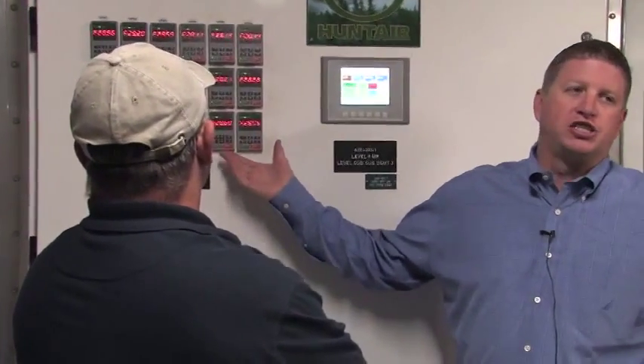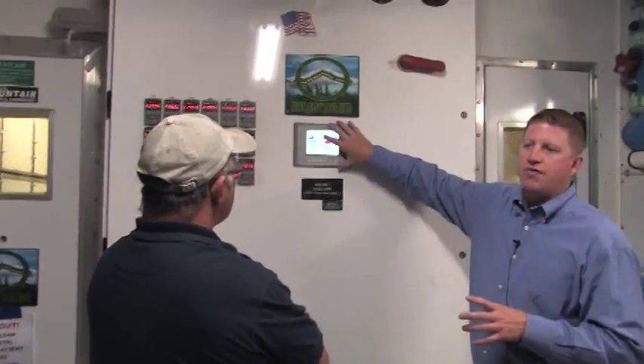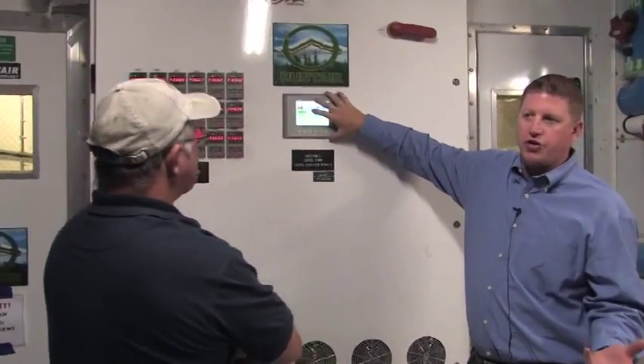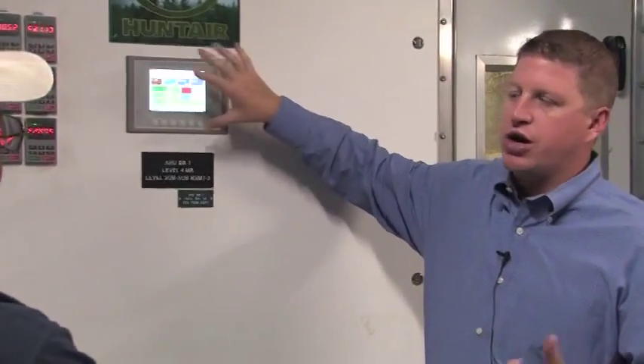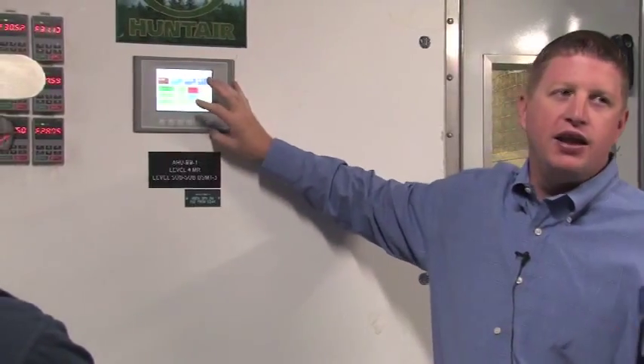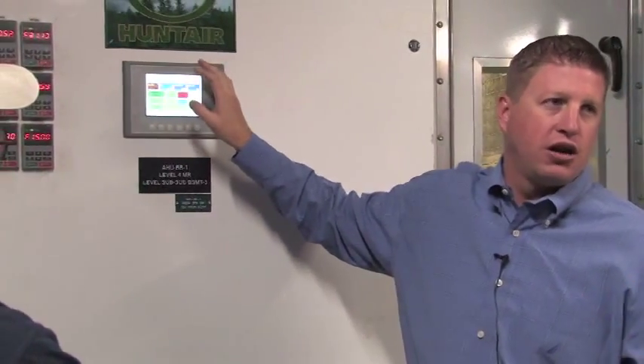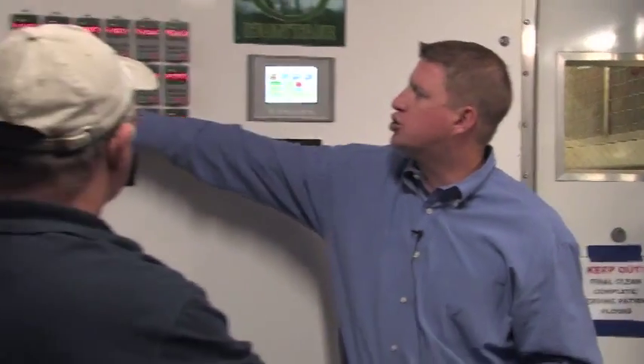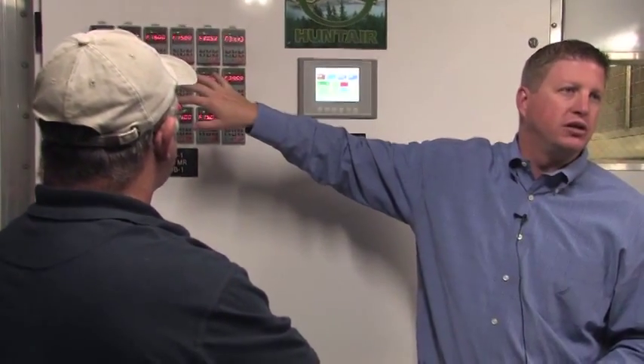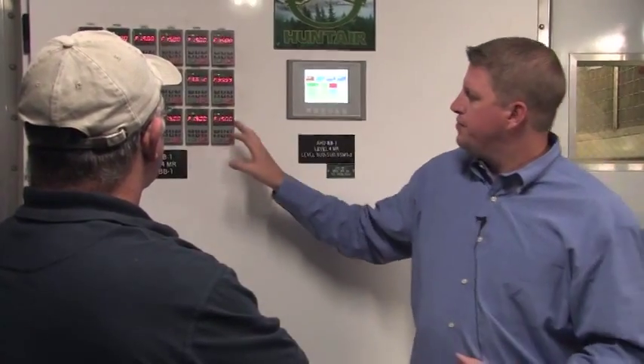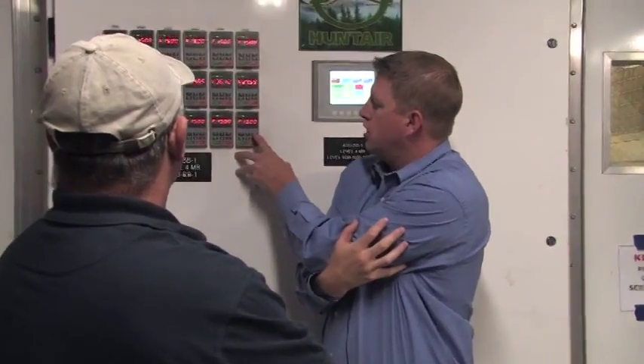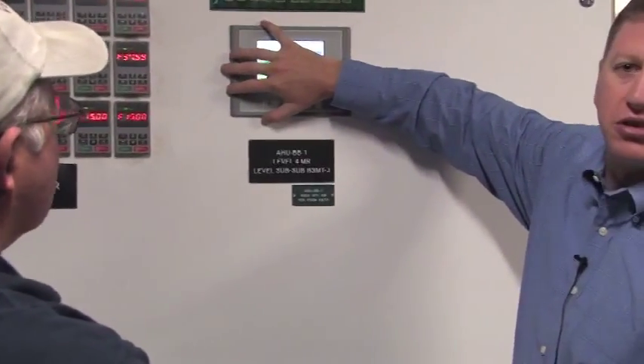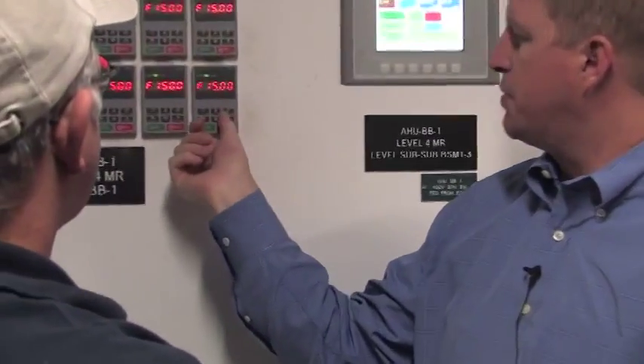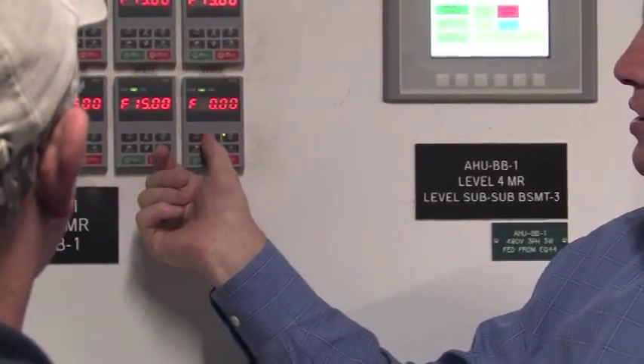So we're going to go through actually a scenario. The levels of redundancy are very deep in this, in that if this screen were to ever die, you could still control the unit through the BMS. In a situation where you lost this screen and the BMS, you could actually still get it up and running, and I would control each of these drives individually. To do that, I'd simply push this local and remote button. This is dead, let's ignore this screen.